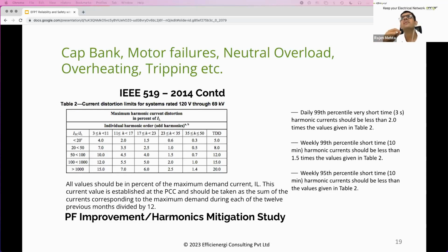If you have a load size which is very small, say in the 5 to 10 kilowatt range, then you need it to be compensated with an equally small capacity of reactive power compensation steps. Alternatively, an SVG, static var generator, solution can work very well in low load, high load, any kind of situation, because it mirrors the amount of compensation in a stepless manner. It doesn't have step requirements. It can work completely stepless in your facility.